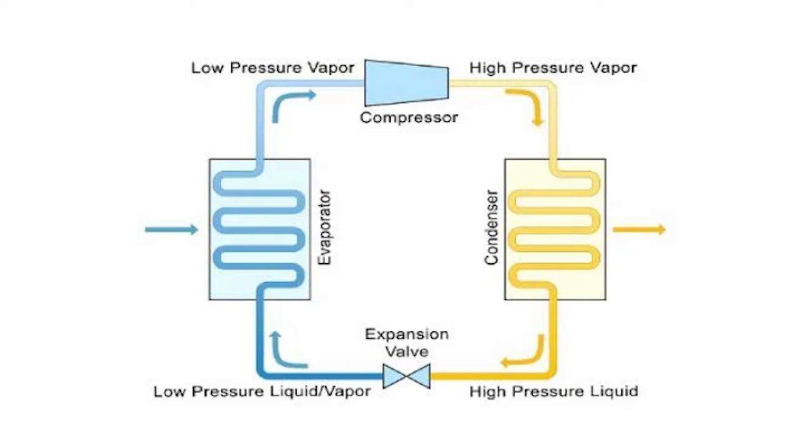For the evaporator to absorb the heat from the area being cooled, the refrigerant liquid entering it needs to be at a very low temperature, for the difference to be sufficient for the heat exchange. This is done by lowering the pressure of the refrigerant entering the evaporator, thereby lowering its temperature too, and the metering device serves this purpose. The two most commonly used metering devices are the capillary tube and expansion valve.